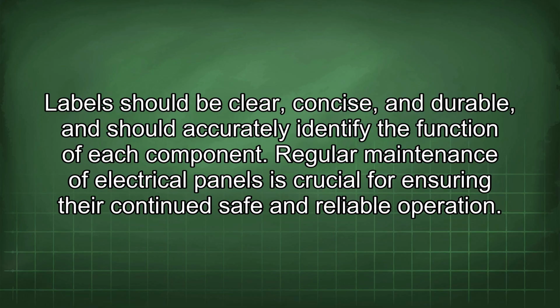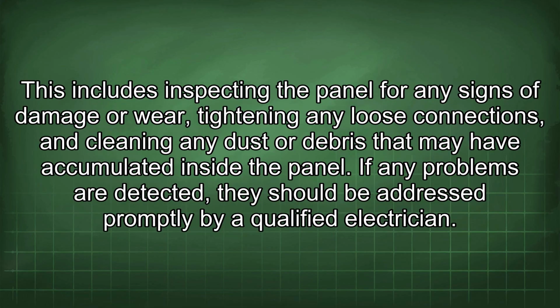Regular maintenance of electrical panels is crucial for ensuring their continued safe and reliable operation. This includes inspecting the panel for any signs of damage or wear, tightening any loose connections, and cleaning any dust or debris that may have accumulated inside the panel. If any problems are detected, they should be addressed promptly by a qualified electrician.